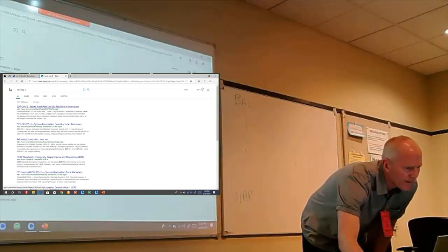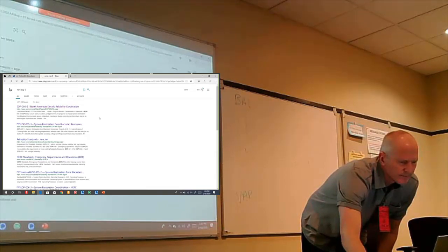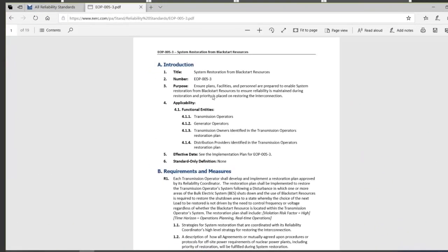So you have to energize the island. You have to check for maintaining stability on the interconnected island, and then also when you connect island to island and create the bigger island, the full network, then you have to run stability and make sure that you maintain synchronism. You don't have units go out of step. You don't violate the nuclear requirements, et cetera, et cetera.